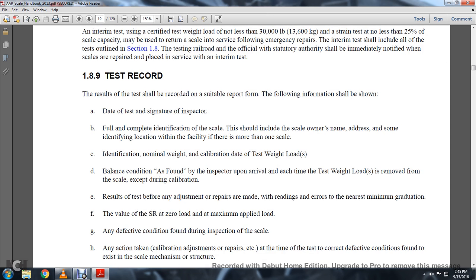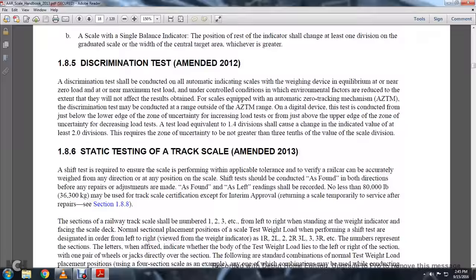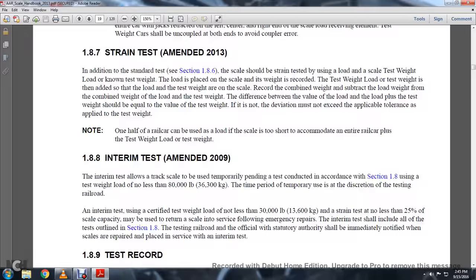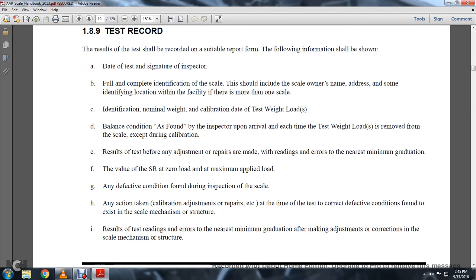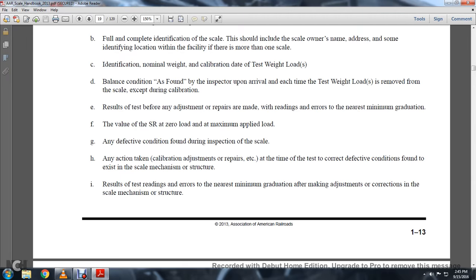Scale identification, nominal weight, calibration date, and test weight load. The balance condition as found by the inspector upon arrival. Each time the test weight load is removed from the scale — except during calibration — results of the test before adjustment or repairs, readings, the error in minimum graduations, value of the sensitivity requirement, zero load, and maximum applied load. Any defective condition found during inspection or testing of the scale, any action taken by way of calibration adjustment, repairs at the time of test, and corrective defective conditions found in scale mechanism and structure.